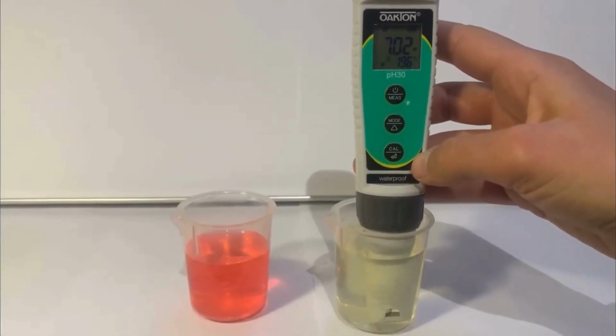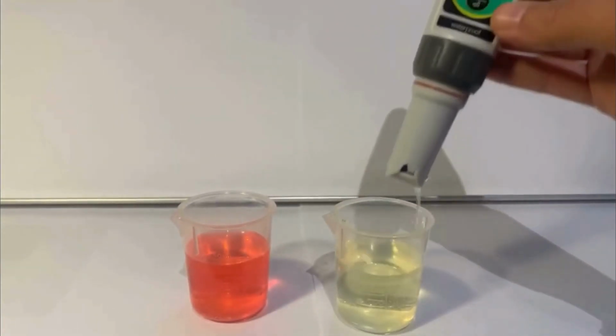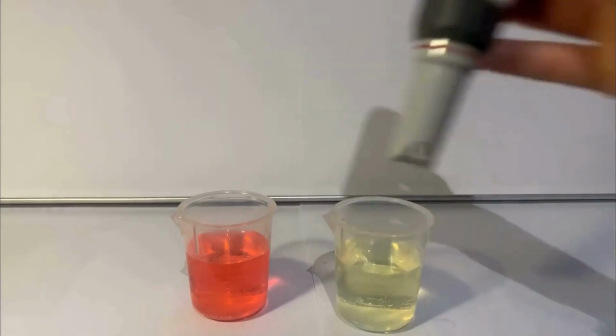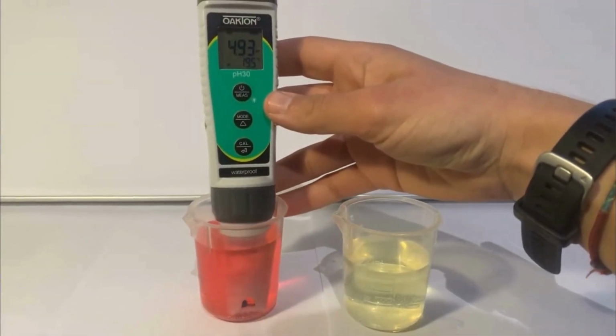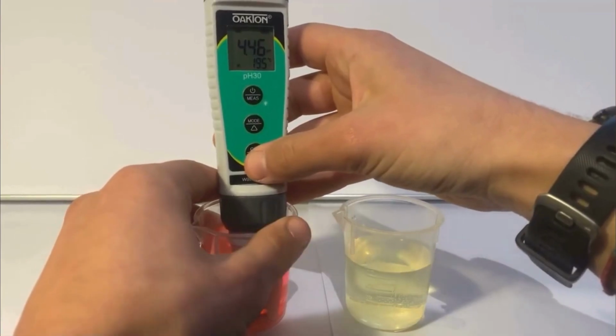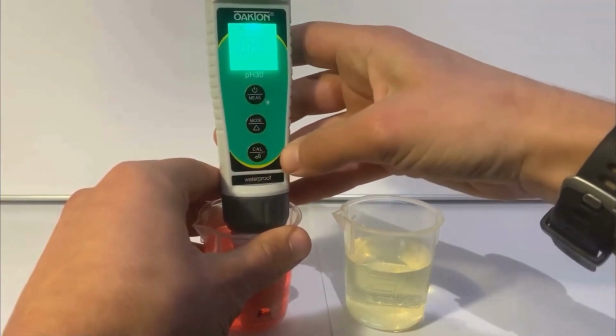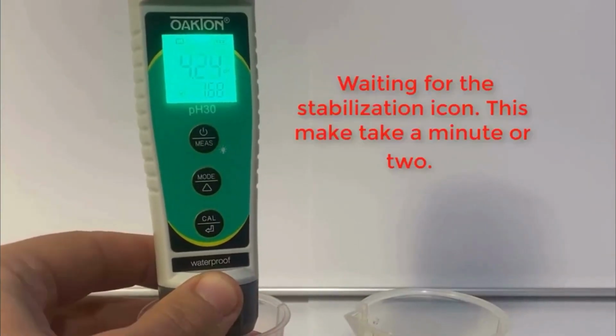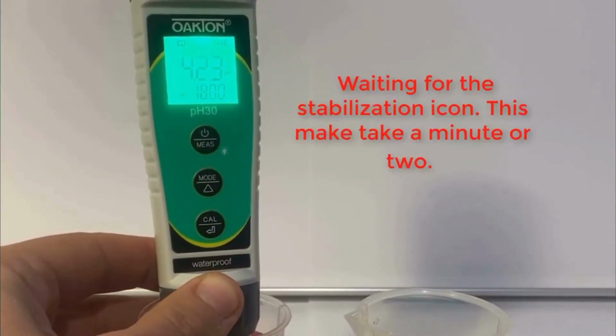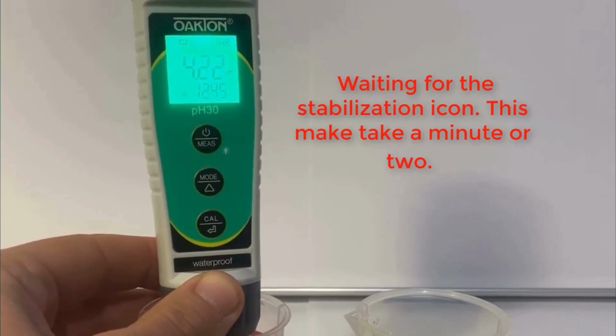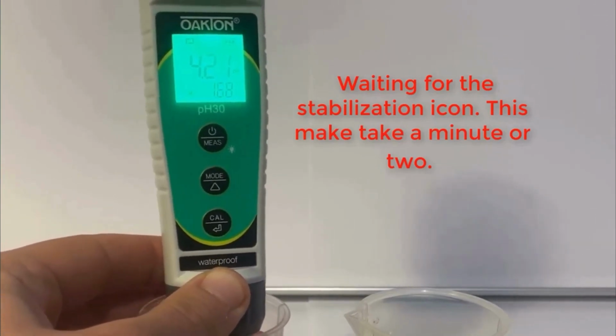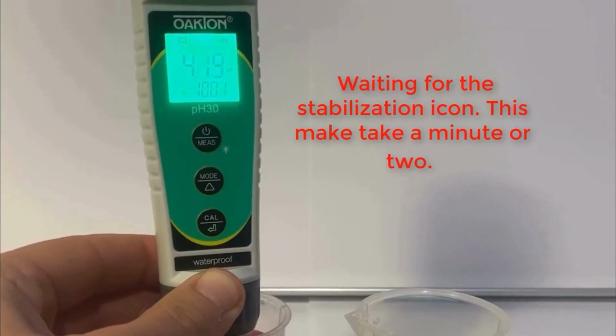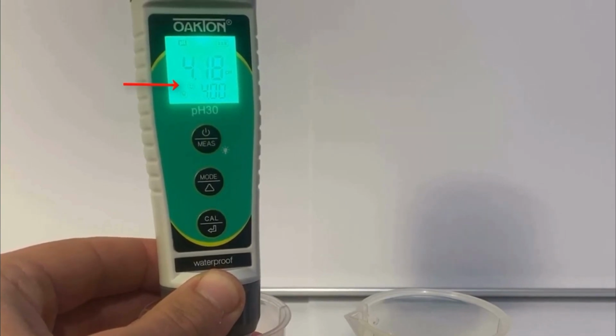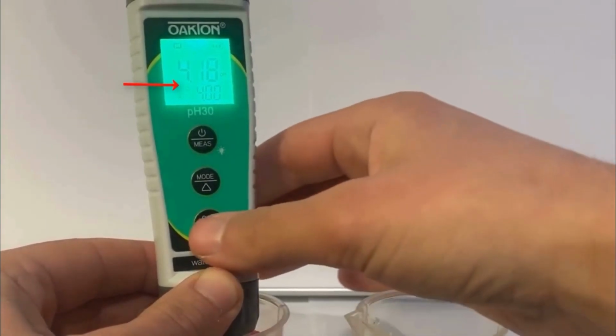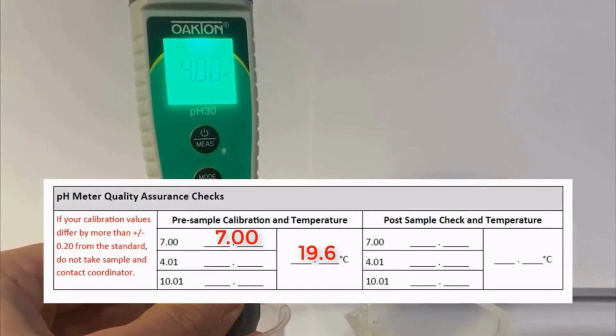Take out your meter, rinse it thoroughly with water, and repeat this process in your next calibration solution. Place your meter into Buffer 4 solution, long press CAL to enter calibration mode, and wait for the stabilization icon to appear. Short press CAL to save your calibration. Record the number that flashes on your datasheet.